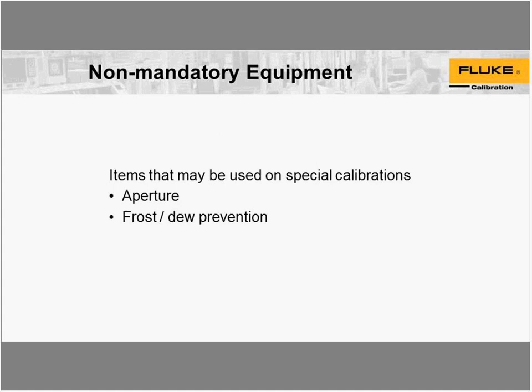There's some non-mandatory equipment that may be used on special calibrations. One such item is an aperture — there are a few models of IR thermometers that do require an aperture for calibration. For Fluke models, I'm thinking of the Raytek MX series — MX2, MX4, MX6 — they required an aperture and a certain measuring distance. Those models became the Fluke 572, 574, and 576. I don't see a lot of those models in the field in the United States, though I was in an email conversation with a customer a few weeks ago who does get those models in periodically for calibration.